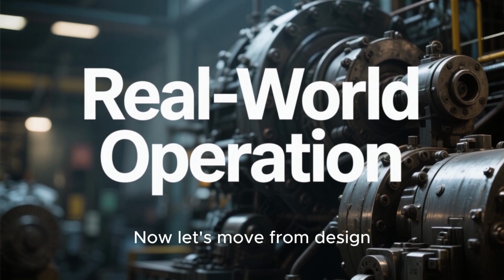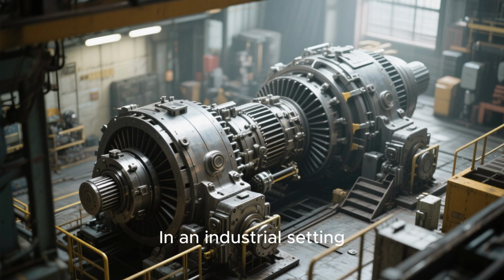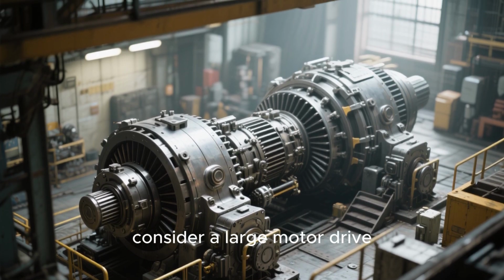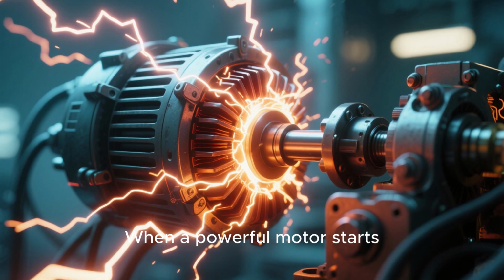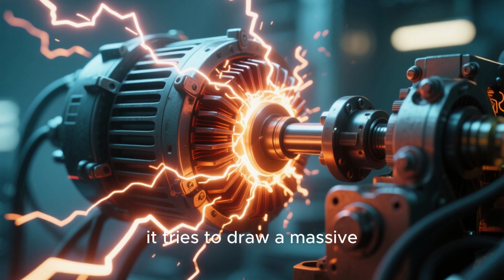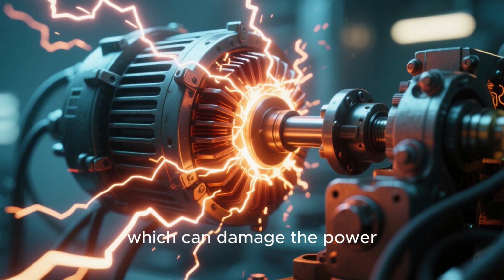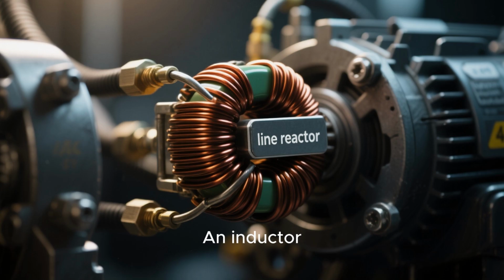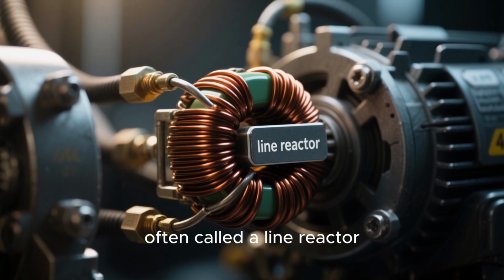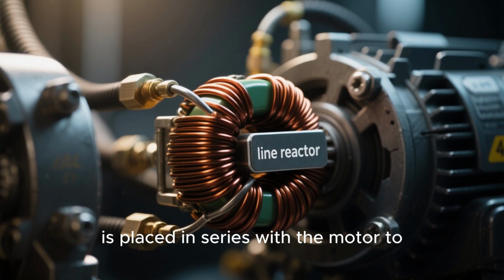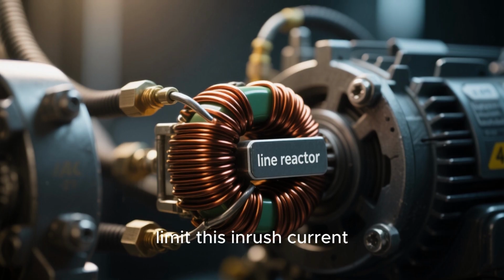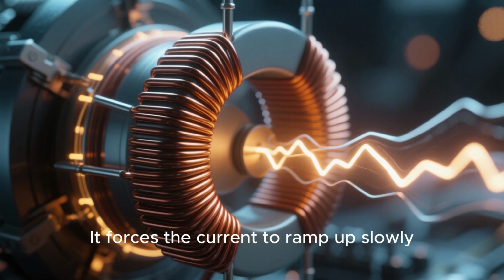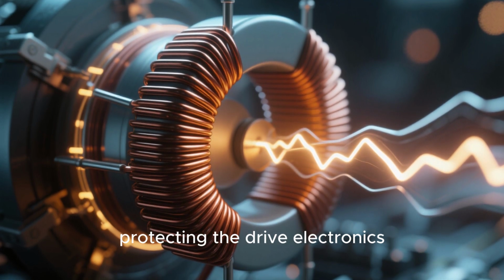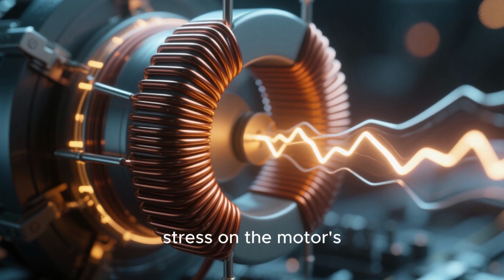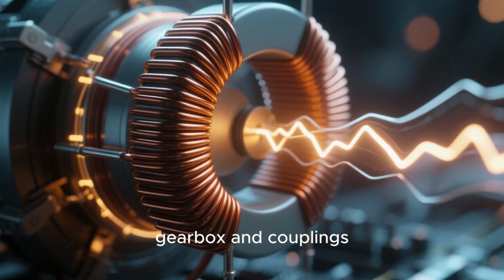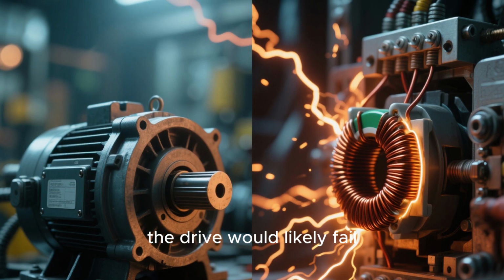Now let's move from design theory to real-world operation. In an industrial setting, consider a large motor drive. When a powerful motor starts, it tries to draw a massive amount of current, which can damage the power electronics or even the grid. An inductor, often called a line reactor in this context, is placed in series with the motor to limit this inrush current. It forces the current to ramp up slowly, protecting the drive electronics and reducing mechanical stress on the motor's gearbox and couplings. Without that inductor, the drive would likely fail.